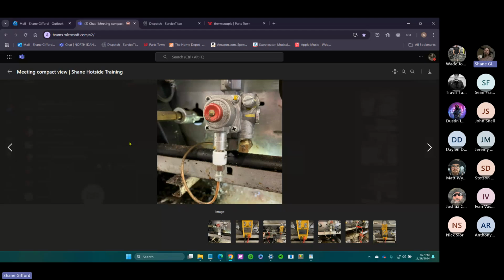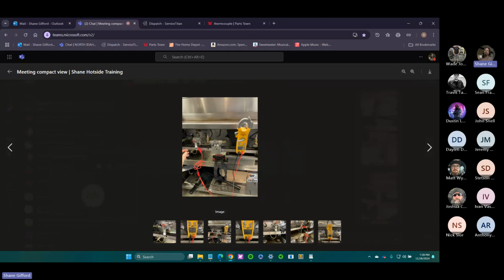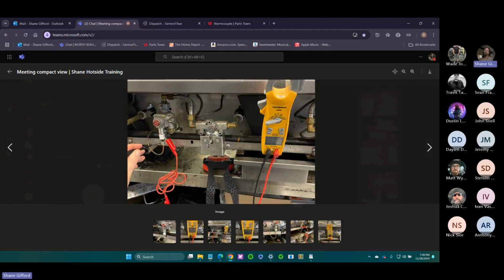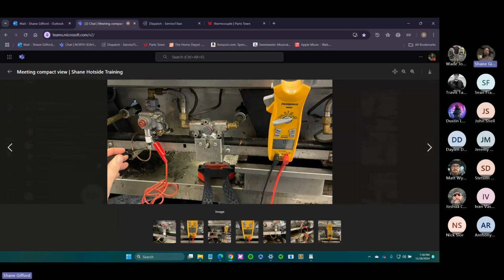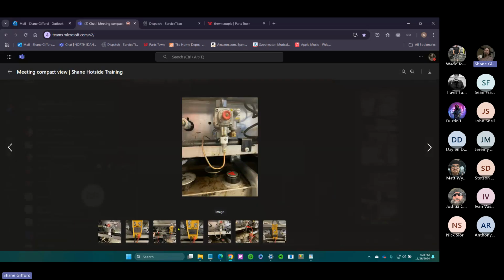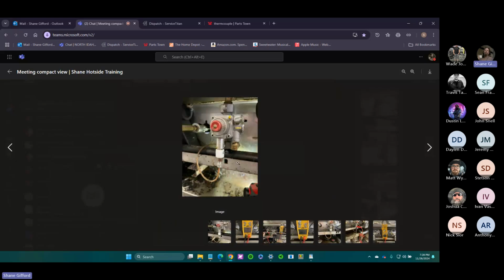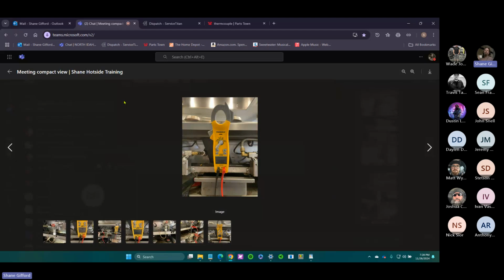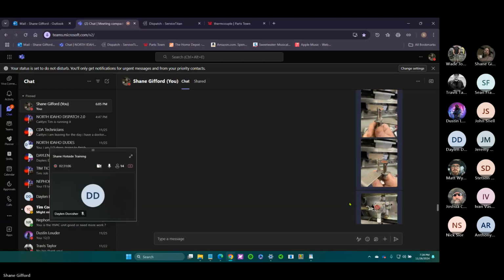But doing jobs like that is cool too, because it gives you an opportunity to take these things apart and see how they're put together and how they function. Like this one in particular, instead of having a combo gas valve like the Honeywell ones and the Pitco fryers, the pilot valve is actually separate from the burner valve. So this pilot does its own burner. That's the far left one. But I think I have a picture of one that is split with the hood. On these ones, you'll have one pilot valve that does 2 burners.